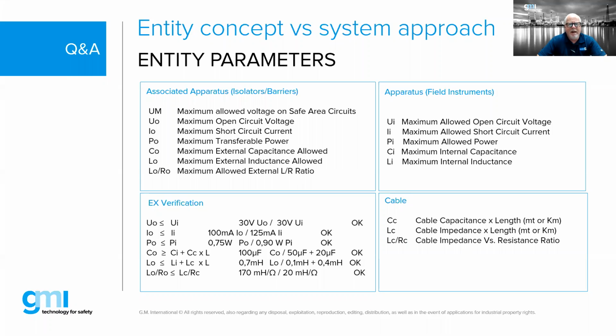Here's a great example. For our associated apparatus, which is the barriers, we'll have this type of information from the manufacturer, such as the maximum allowed voltage. Our EX verification at the bottom is basically what the verification tools will check, making sure our voltage output doesn't exceed the input to the device, and the power output doesn't exceed the power input, and so on.